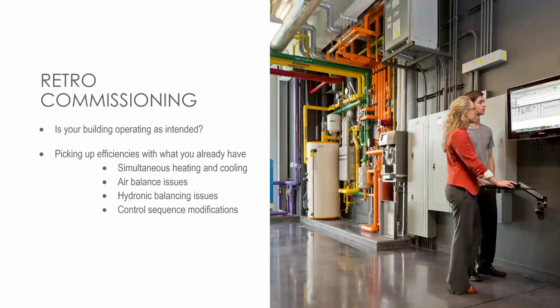We see simple things all the time. One of the most common is a hot water coil that's always on just a little bit, so you're always simultaneously heating and cooling your air. Not only that, but your fan's running all the time because you're not delivering 55-degree air anymore, you're delivering 65-degree air.